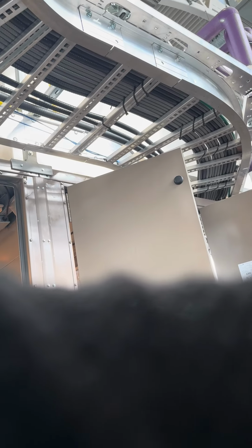Now, this is kind of called the economizer, right? So we can either open this area here and send 100% of the air up outside the building as exhaust air, or we can keep that closed and have 100% of the outside air come in as supply air. And any percentage of mixing between those. So we can go 100 to 0, we can go 50 to 50, we can adjust it so we maximize it, right? In the winter, we're spending a lot of money to heat the air. We're going to return a lot of the return air and use it as supply air. So this is our mixing chamber where we start to get all of our exhaust air and outside air mixed up together.